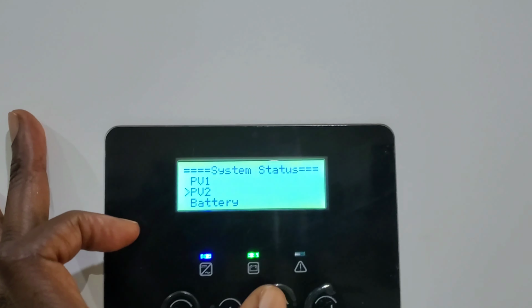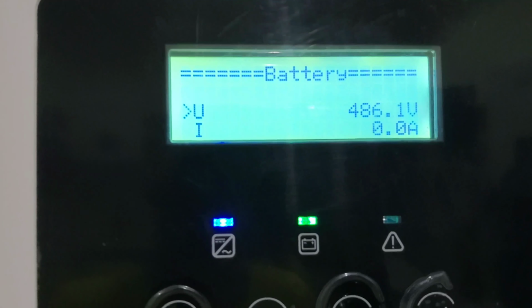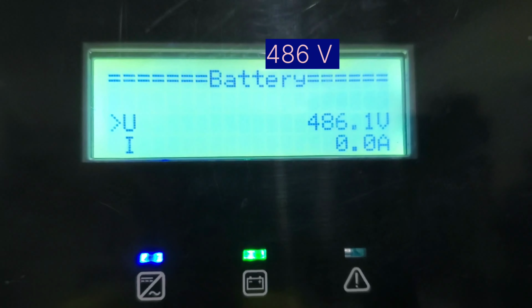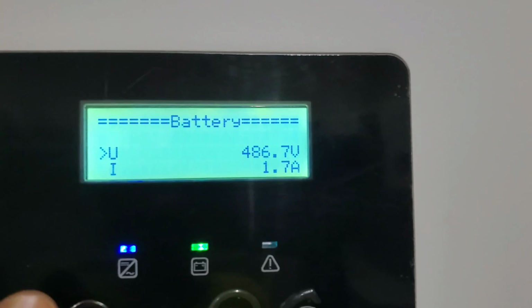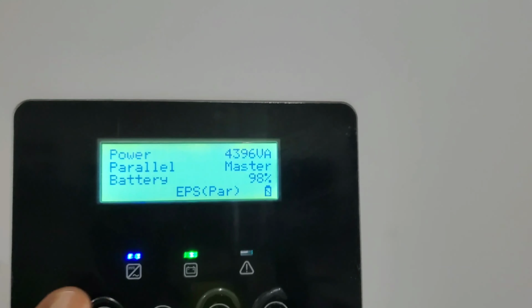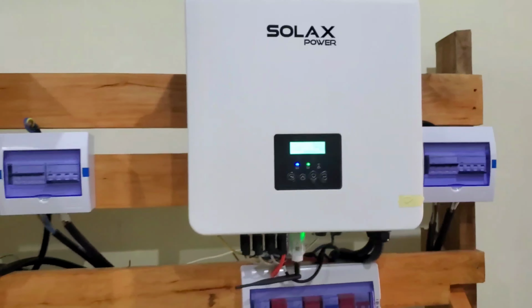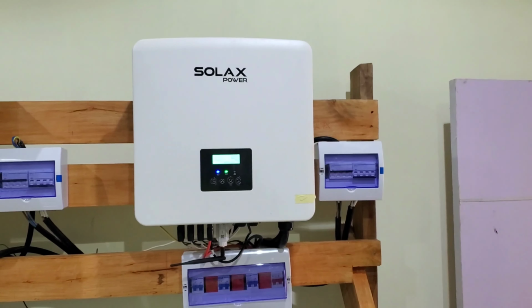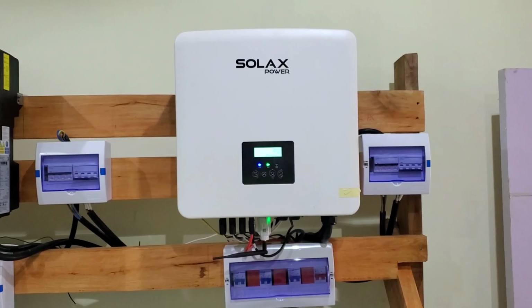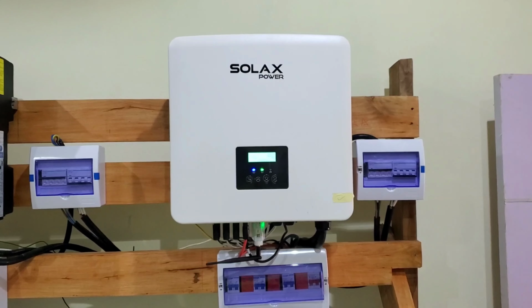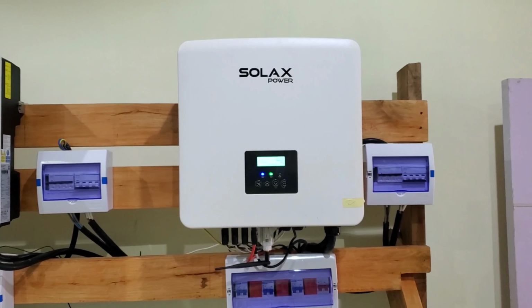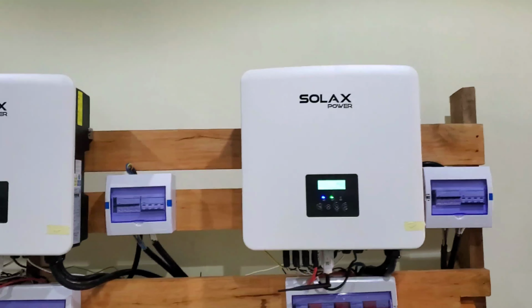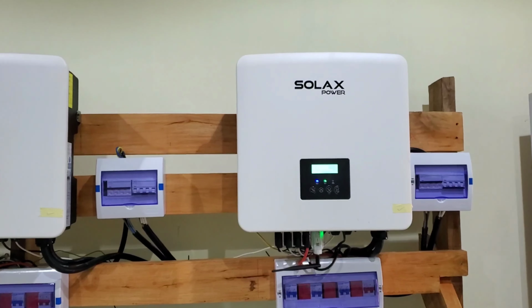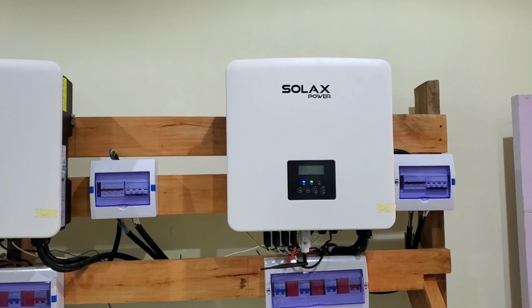Battery voltage. Give me a second. What do you see there? Can you read it? That is our battery voltage, 486 volts. Like you see, 0.0 amps because our batteries are full and our PV is powering this directly. So on each inverter, we have about 20 kilowatts in PV, which is 2 kilowatts more than the manufacturer suggests we put on the inverter. And we figure we'll never get to 18 kilowatts. Very rarely are we going to see that number. But if we see 16, we're very happy. And I doubt it very much we'll ever see 16, unless the batteries are completely drained and the load demand is high, then we might see that.